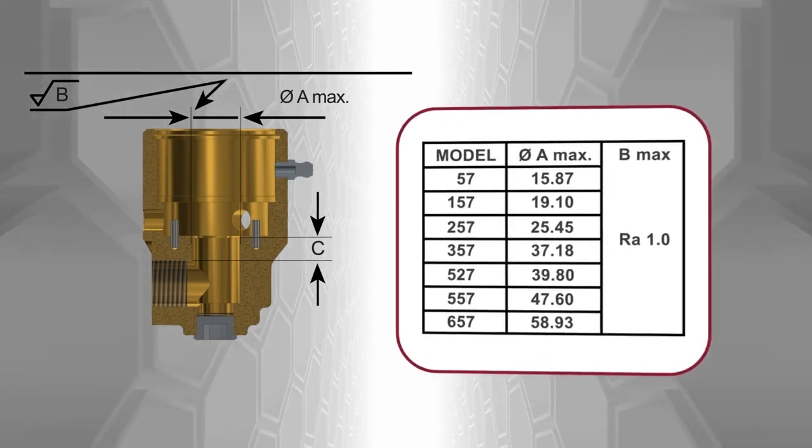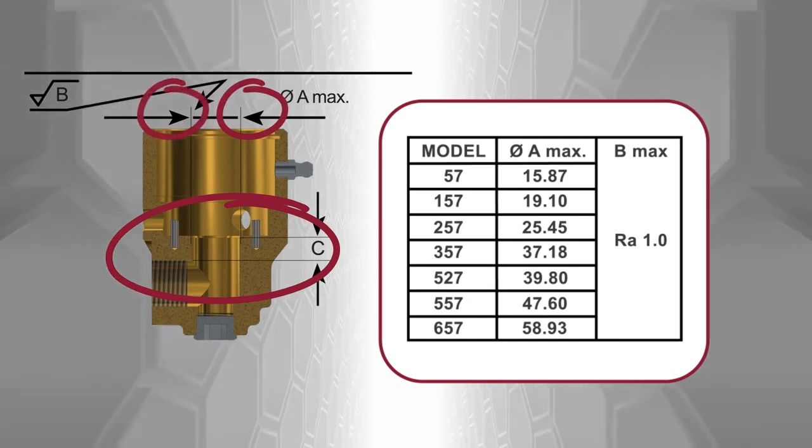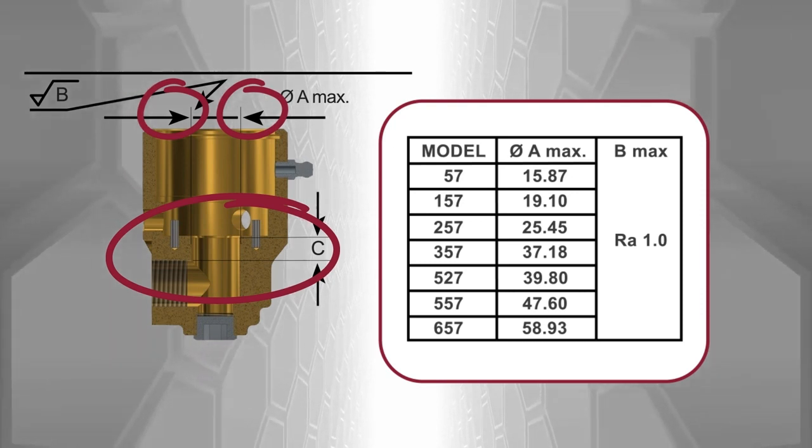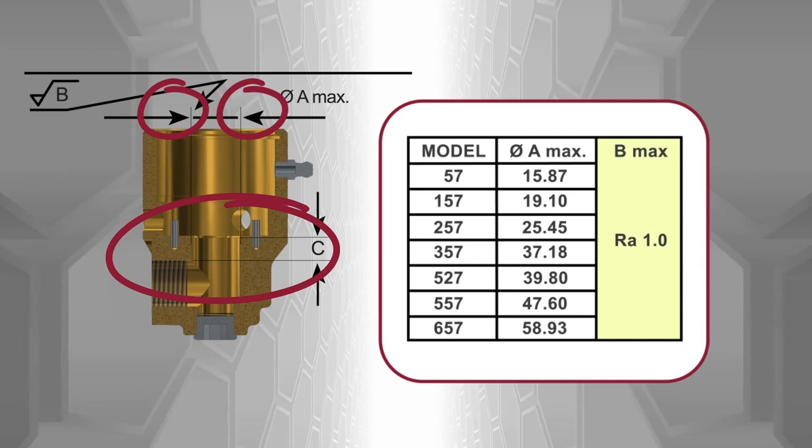Within the area labelled C, the bore surface must be smooth to a maximum roughness level value B. For all 57 series models, the maximum roughness value for B is RA 1.0.